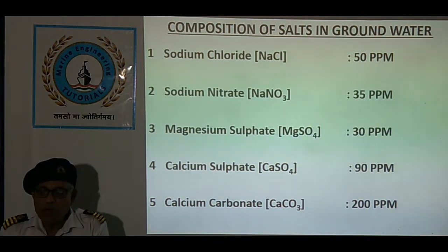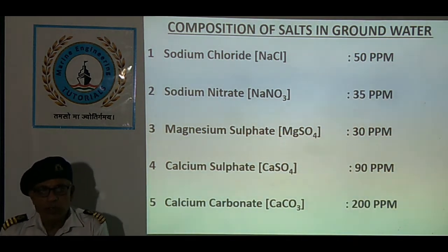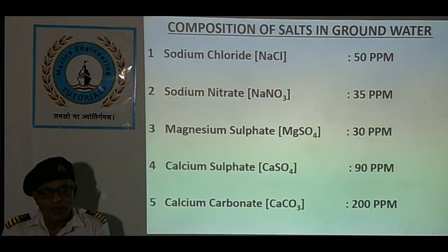Only evaporated water should be used as makeup water for boiler feed, as ordinary shore water contains enough salts which exceed the maximum allowable limits prescribed by boiler manufacturers. Shore water may only be used in smoke tube boilers, that too in extreme emergency.